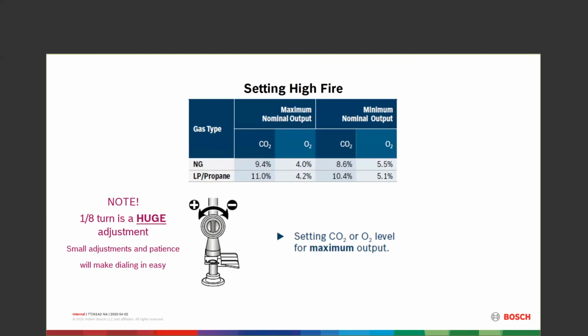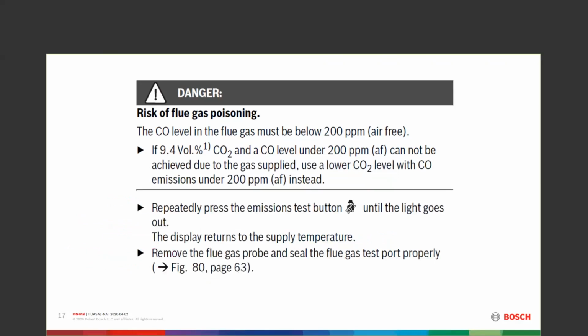Go up to high fire, start on your high fire adjustment. If you're high, you're going to start bringing it down. If you're low, you're going to start bringing it up. Don't take it all the way if it's way off. If it's off a half of a percent, that's okay. Take it. If it's off more than 1 full percent, you absolutely want to go easy on that and take small bites. You're just going to move from high fire to low fire and then back up to high fire, down to low fire, giving your analyzer a little bit of time to actually compensate for what's in the lines and get a good reading.